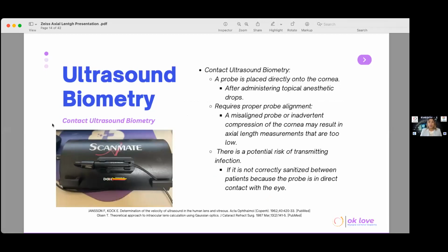With ultrasound, one of the advantages is because we're using a scleral lens and we're filling it up with the saline solution, there's no direct contact to the cornea, so that is going to be beneficial when we compare it to the contact biometry, because we are minimizing the compression factor to the cornea, which can sometimes give us results that are not as accurate. It could also give us an underestimated length reading. So when we are choosing to purchase a biometer for our offices, because we want to start monitoring axial length, it's important that we keep these different points into consideration.